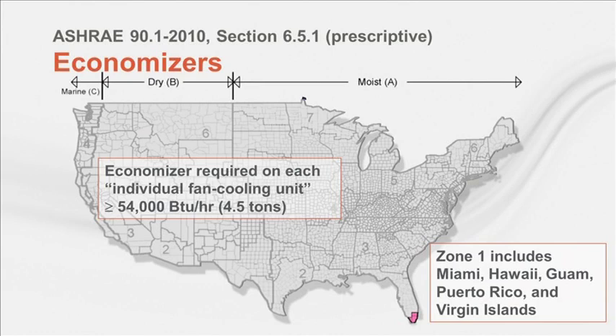The next requirement we'll discuss is for economizers. The standard 90.1 requirement for an economizer depends on system size and climate zone. In the 2010 version, either an air or water economizer is required on each system 4.5 tons or larger, in every climate except Zone 1. But just like in the case of the fan power limitation, each indoor VRF terminal is considered a fan cooling unit. So if an indoor VRF unit is smaller than 4.5 tons, which is typically the case, an economizer is not required. In your handouts, I've included an excerpt from an example in the 90.1 user's manual that explains this.